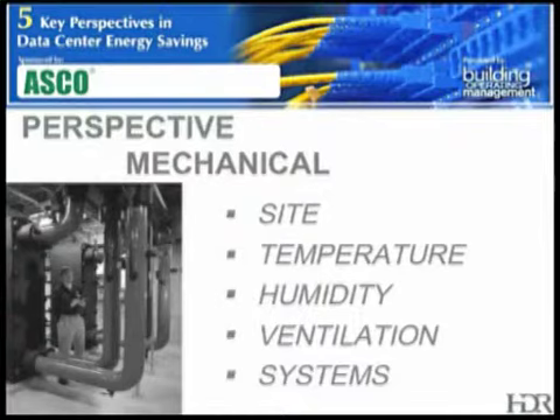I think the ventilation rates for data centers are often driven by a couple things: making up for exhaust from spaces such as battery rooms, and also providing positive pressurization for the building to minimize uncontrolled infiltration. We don't really want the temperature or relative humidity impacts of air migrating into the facility, so if we keep it under positive pressure, we can control it. And if you do have a ventilation system that's tied to providing your active humidity control, that air handler may bring in that outside air, provide humidification when needed, and may recirculate some of that air from the data center back out as part of a dehumidification cycle.